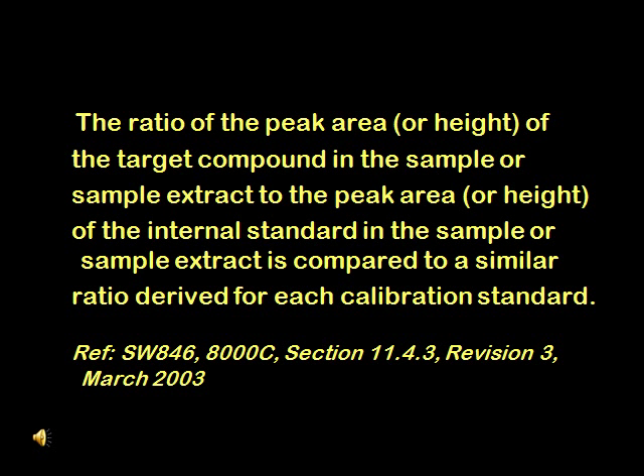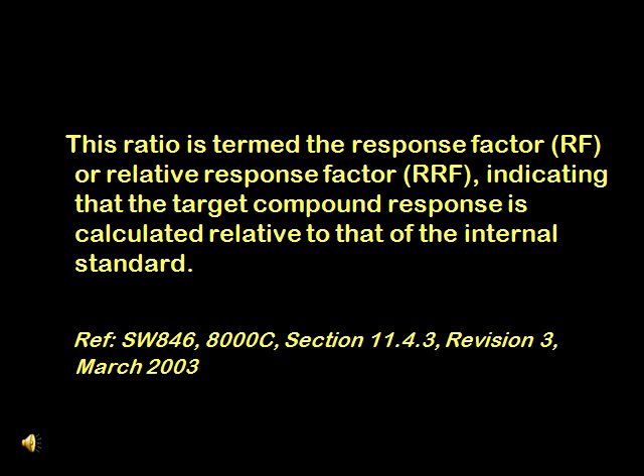In the internal standard calibration, the ratio of the peak area or height of the target compound in the sample or sample extract to the peak area or height of the internal standard is compared to a similar ratio derived for each calibration standard. In the case of metals analysis, the emission counts of the internal standard in the sample or extract is compared to a similar ratio derived for each calibration standard. This ratio is termed the response factor, RF, indicating that the target compound response is calculated relative to that of the internal standard.